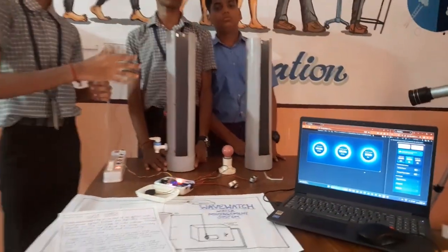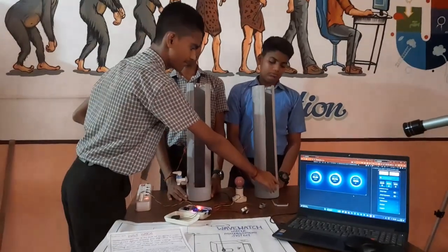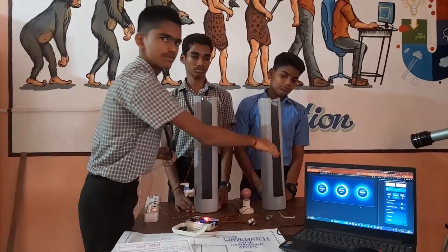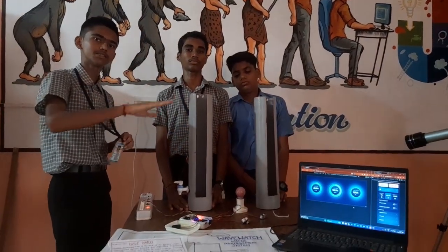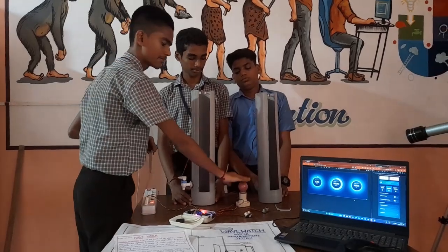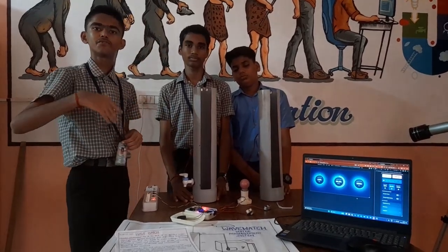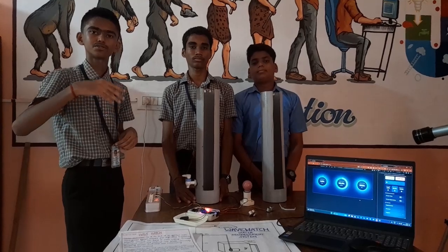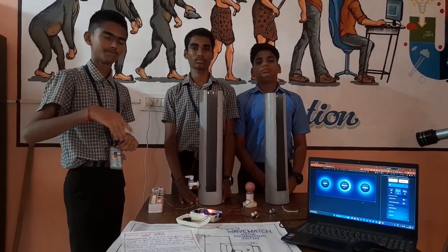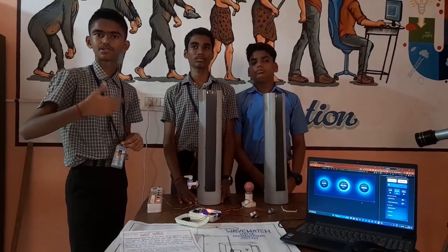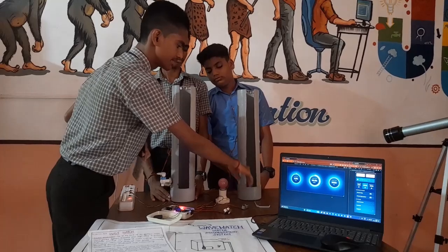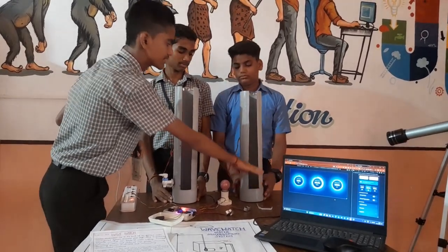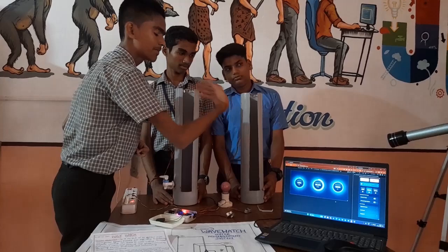So this is just the working, but the main logic of the system is that here the pump will be there. So when the water level is lower than 10%, meaning when it is lower than the pump's level, then automatically the pump will turn off. By doing this, the pump will not get damaged because running without any water will damage the pump. So we are putting a lower limit over here, and in the same way, when the water level reaches 50%, then the pump will turn on.